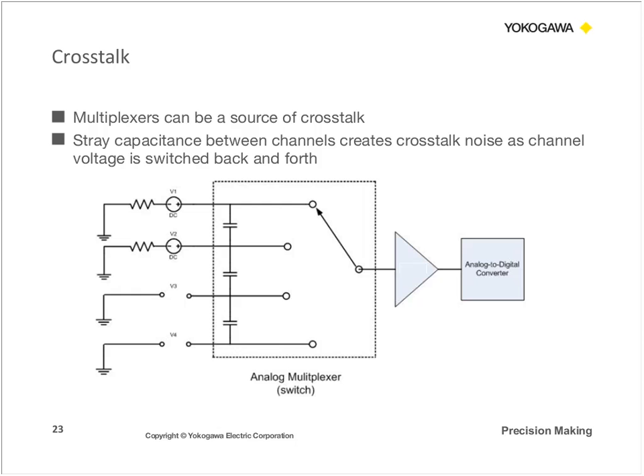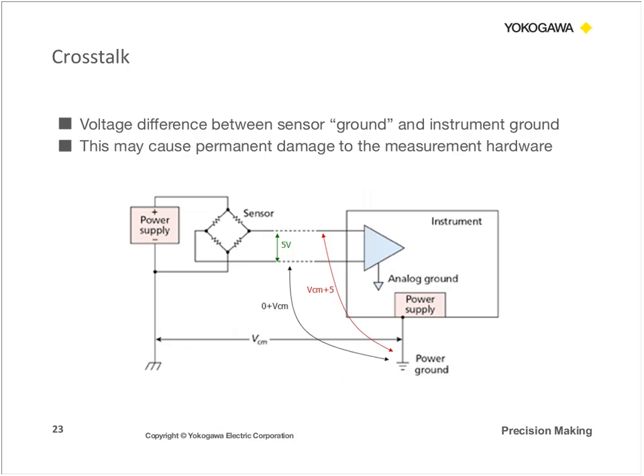So what you're going to see is that voltage or that noise carries over from one channel to the other. And in effect, the capacitance has less time. The faster your signal is, the less time it has to bleed off its charge before it reaches the A to D conversion. And an instrument with built-in isolation amplifiers on each channel is really what's needed to solve this problem.